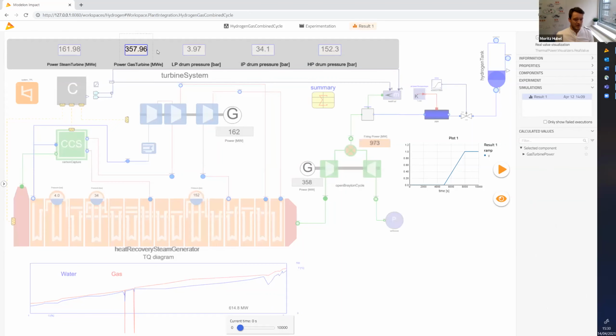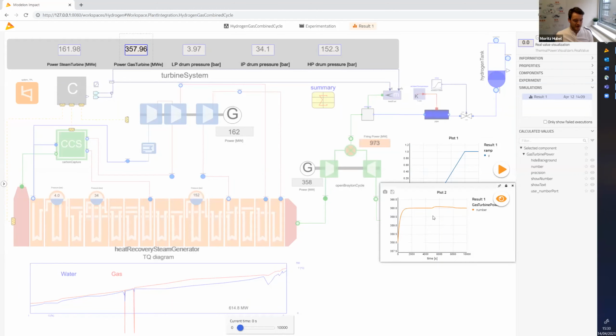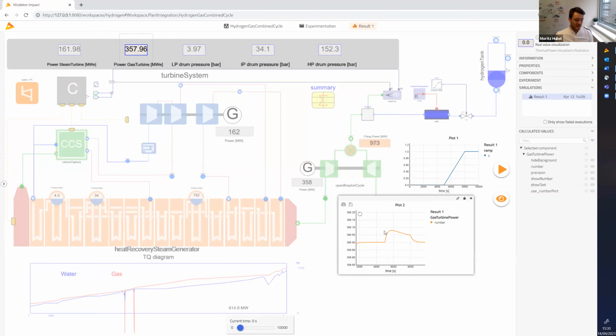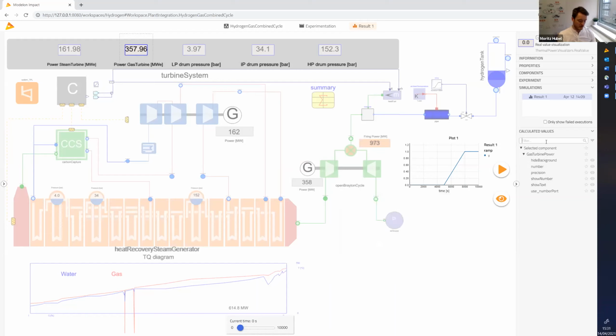If we look at the gas turbine power, we can verify that's true. The gas turbine runs at a nominal power of 360 megawatts, so large scale. We see some control behavior happen when we change the hydrogen content, a disturbance, but after a short time the controller manages to balance the load again, back to 360 megawatts. Now we can also investigate the hydrogen share.